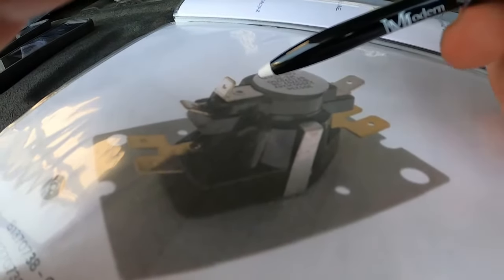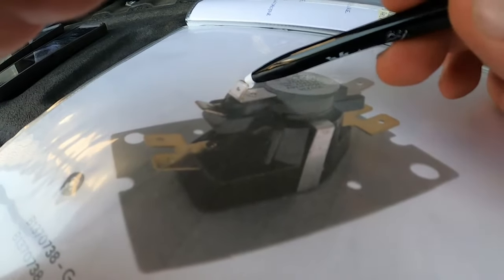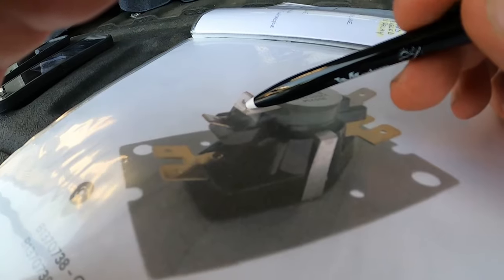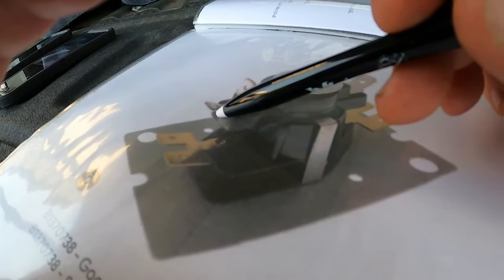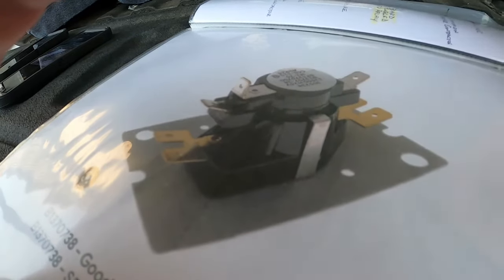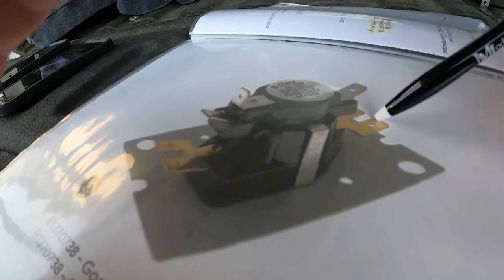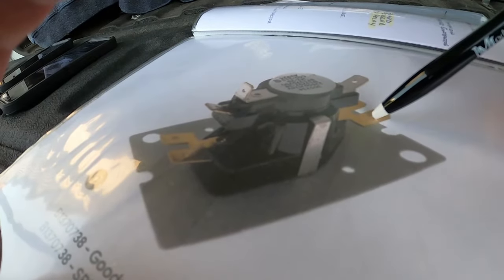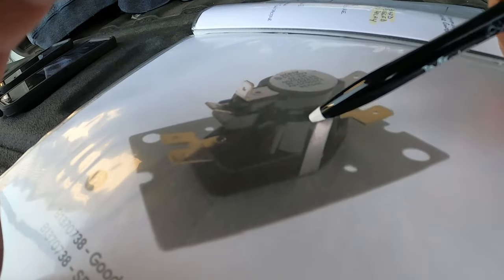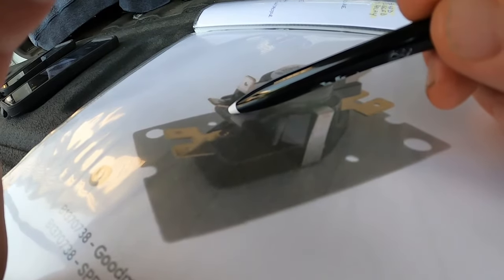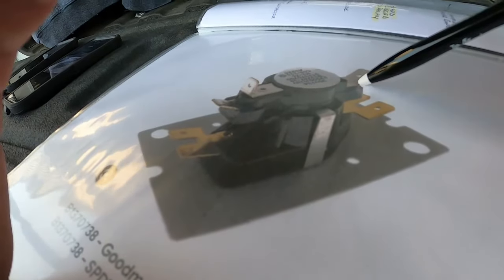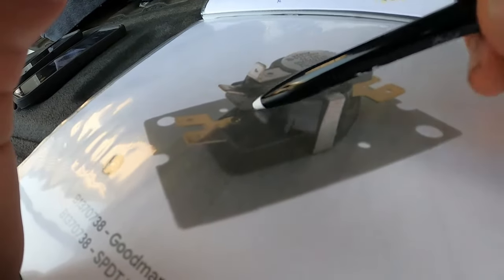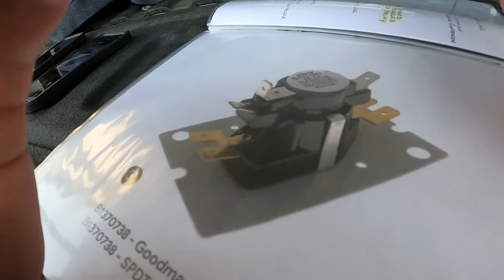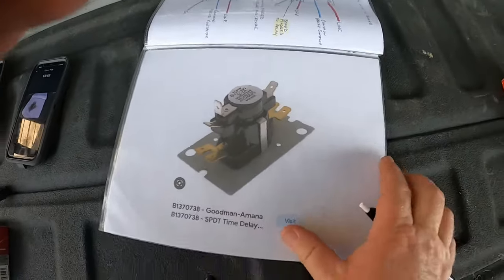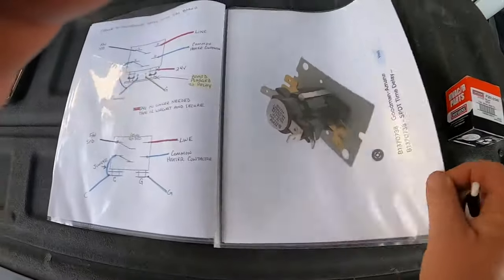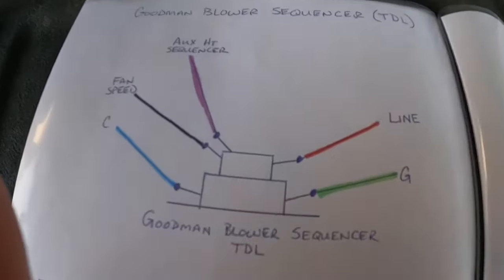So if your heat strips were to come on, you have a back feed that comes in. You get a line of power here, energizes the blower, it comes on, and you've got airflow with the heat strips running. If you get a call from the thermostat for regular heat pump or cooling operations, you just energize here with your low voltage, and then when that switch closes, it connects your common, which is your fan speed, over here to your line voltage in, and that powers the blower. This now opens, so you're not going to get a back feed to your heat strips, causing an amp draw on a bank of heat strips. The wiring diagram for that explains just that.